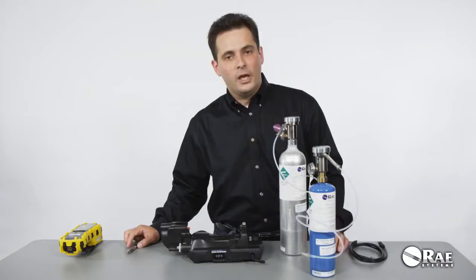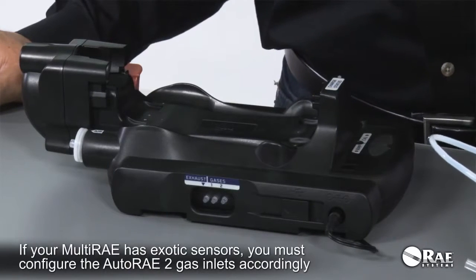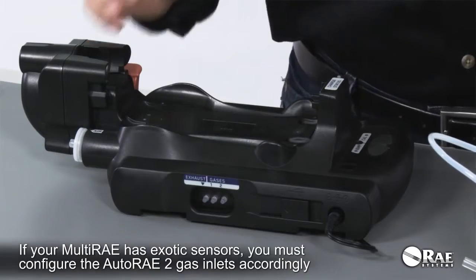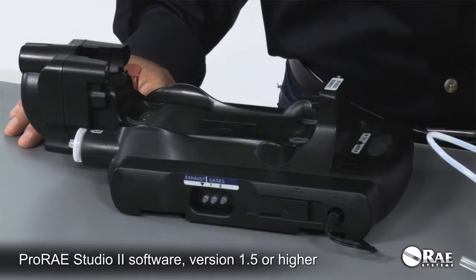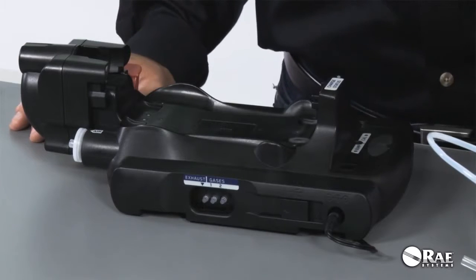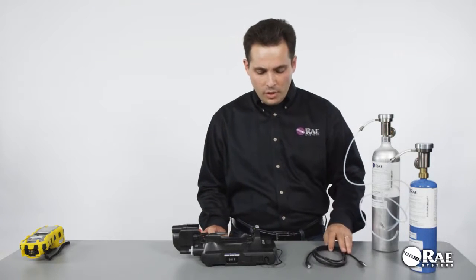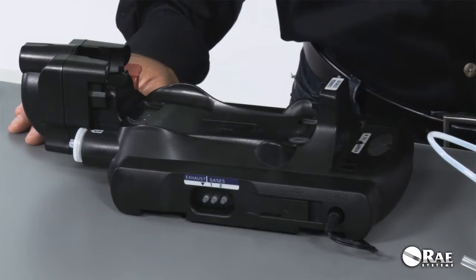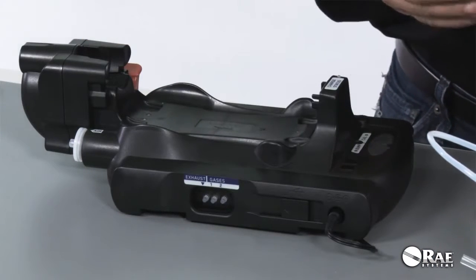It is critically important that if your MultiRAE has exotic sensors in it, you configure the inlets to match the calibration gas you're going to use for those exotic sensors. The inlets can be configured on a PC using the ProRAE Studio II software — version 1.5 or higher. There is a PC communications cable that should be used to connect the AutoRAE 2 cradle to the computer. Once you're done configuring the inlets, make sure to connect the right calibration gas to the right inlet.